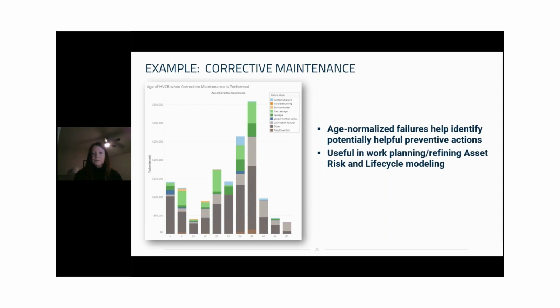So we're really looking at the 30 to 40 year period as the time when these most commonly start to fail more regularly. There's not a lot here in terms of specific failure modes, although with other asset classes we have seen a steep rise in a certain type of failure at a certain age, which has allowed us to recommend preventive maintenance interventions prior to that time to help head off those issues. However, we can recommend here that it's likely worth deeper analysis to determine if we need to perform inspections and preventive maintenance at the same intervals between 10 and 30 years of age as we do on either end of that age scale, particularly because we understand the risk, both probability and impact of failure around these assets, to be relatively low.